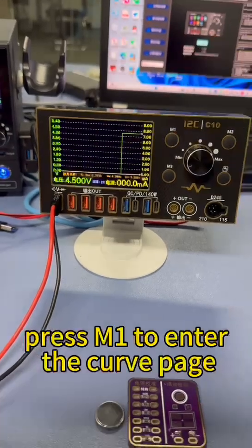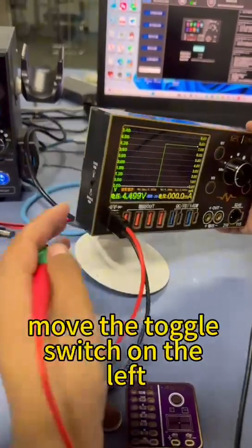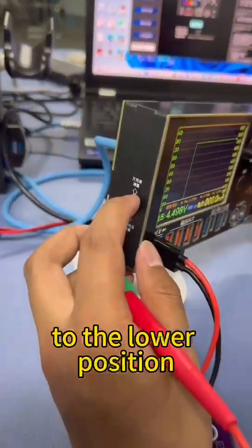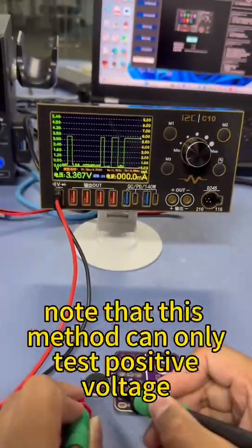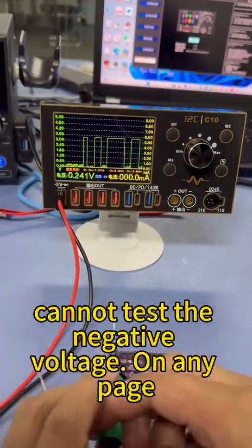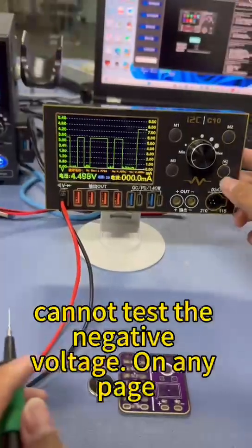Press M1 to enter the curve page. Move the toggle switch on the left to the lower position to measure the voltage. Note that this method can only test positive voltage, cannot test the negative voltage on any page.